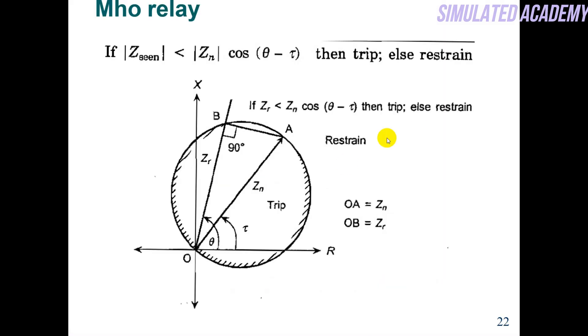As we have seen, Z_seen should be less than Z_n × cos(θ − τ) for the relay to trip; otherwise it will restrain. On the impedance diagram, the x-axis has the real component and the y-axis has the imaginary component — that is, reactance.